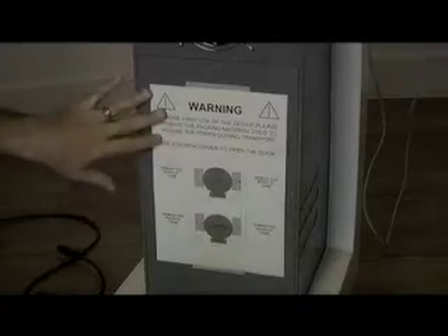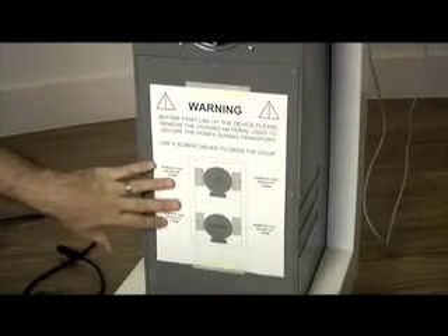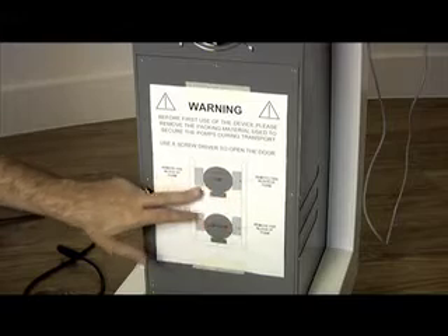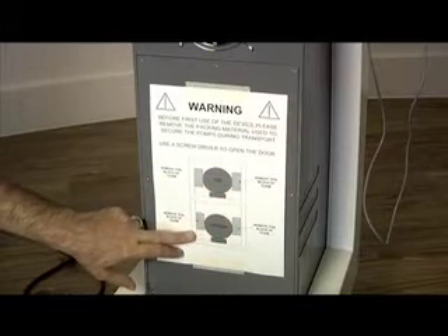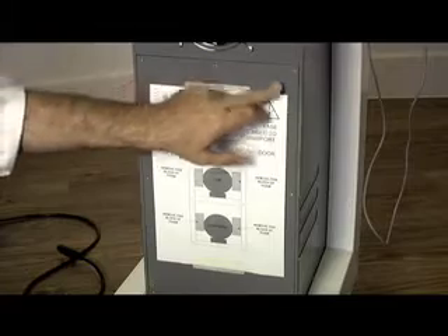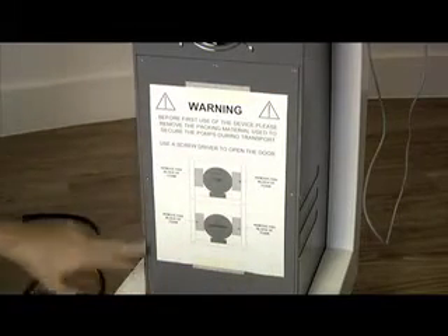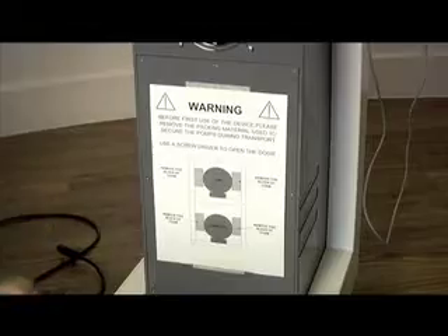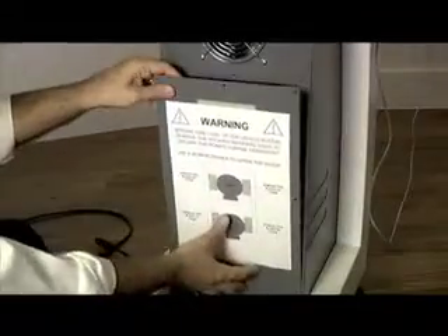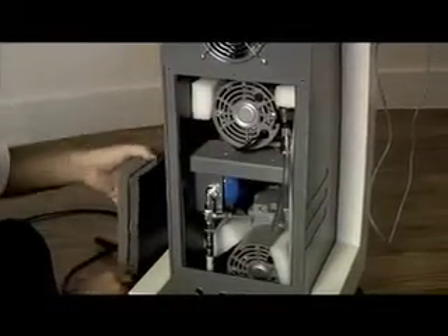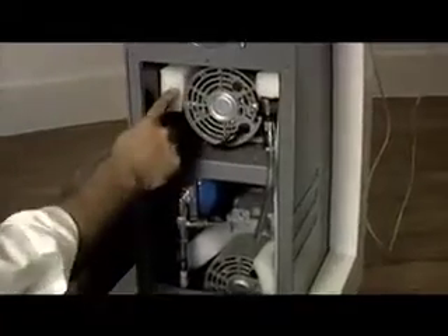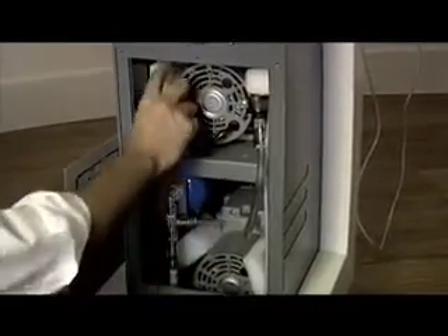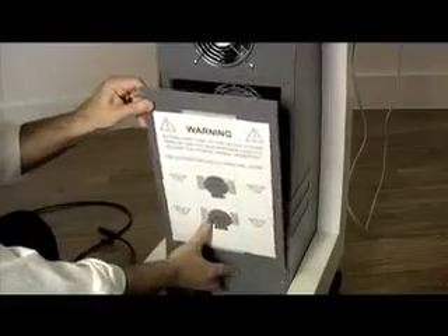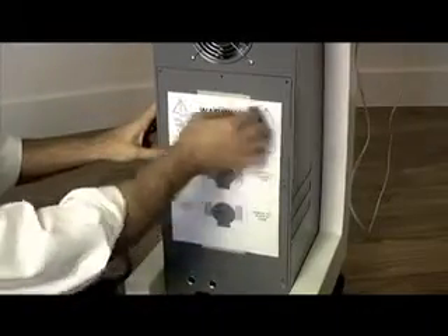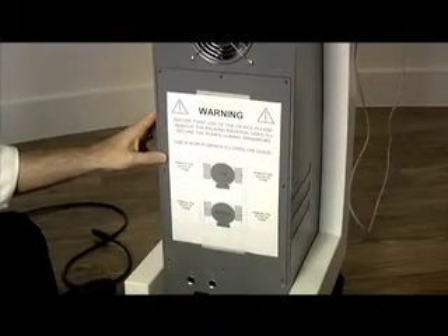Now move to the back of the unit, where you will see a warning label explaining the packing material contained inside the unit to protect the unit during shipping. There are 4 styrofoam blocks, 2 on the top and 2 on the bottom. To remove the back panel, remove 8 screws that hold the panel to the back of the unit. After removing the screws, remove the back panel and remove the 4 styrofoam blocks. Just remove and discard the blocks. Then replace the back panel and replace the 8 screws to secure it to the back of the unit, and remove the warning label.